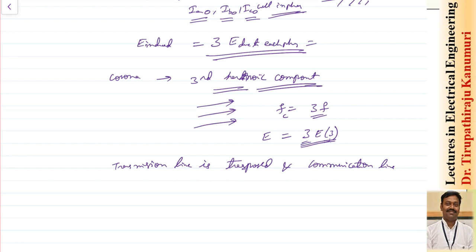To summarize: due to the electromagnetic effect, currents are induced in the communication line. For balanced conditions, transposing the transmission line is sufficient; for unbalanced conditions involving zero sequence or third harmonic components, transposing the telecom line along with the transmission line nullifies the effect. In the next class, we will cover the electrostatic effect and precautions for reducing both effects. Thank you very much.